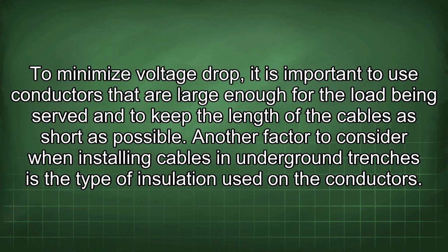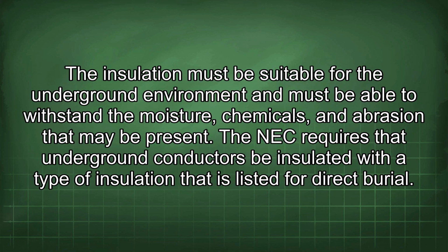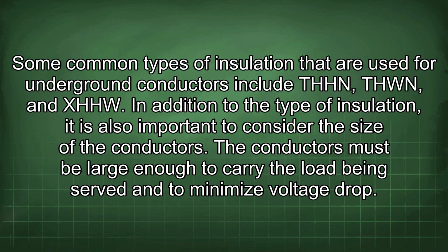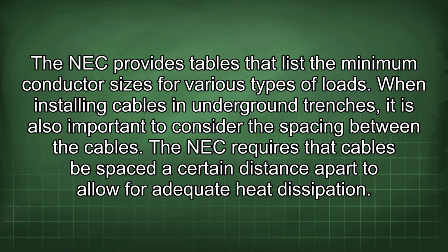Another factor to consider when installing cables in underground trenches is the type of insulation used on the conductors. The insulation must be suitable for the underground environment and must be able to withstand the moisture, chemicals, and abrasion that may be present. The NEC requires that underground conductors be insulated with a type of insulation that is listed for direct burial. Some common types of insulation that are used for underground conductors include THHN, THWN, and XHHW. In addition to the type of insulation, it is also important to consider the size of the conductors. The conductors must be large enough to carry the load being served and to minimize voltage drop. The NEC provides tables that list the minimum conductor sizes for various types of loads.